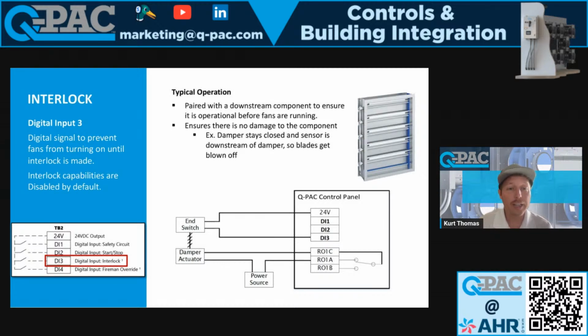So the interlock is disabled by default. So if you do want to use it, make sure you go into the HMI and enable it for use. And we will control dampers for you. So I think it's a great feature. You don't have to rely on the controls contractor to set that functionality up with the building automation system and their controls. It can just be handled locally, which I think is best, because if you do have a failure, then we continue to operate as long as we have power.